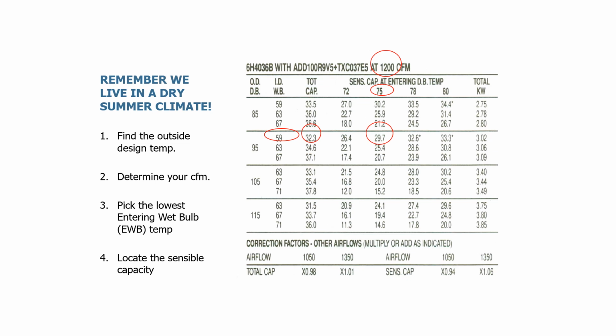We're going to use 1200 because this is a PTCS job and we know we're going to get the correct airflow. So what that means, if you don't have 1200 CFM, if you only have 1000 CFM, these charts are wrong. Pick the lowest entering wet bulb, or EWB, if you will. Indoor wet bulb right here. 59, that's a good one for us.